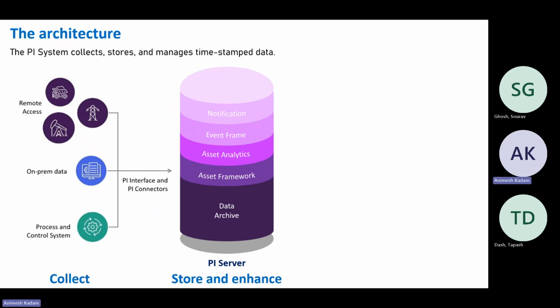So other information like asset framework hierarchy, your metadata, your event frames, your analysis configuration, your template configuration, all this information got stored inside SQL, because the data archive format is only for time series data. The metadata, the tables, your templates, your calculations are not time series data, right?